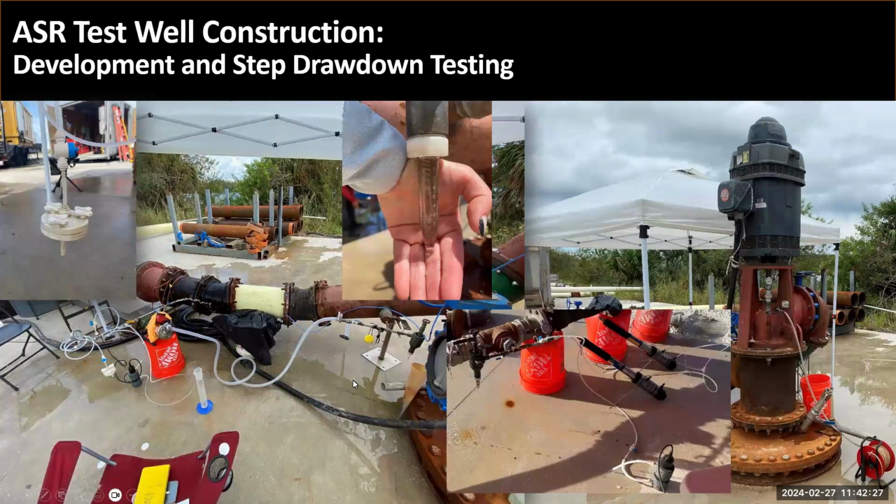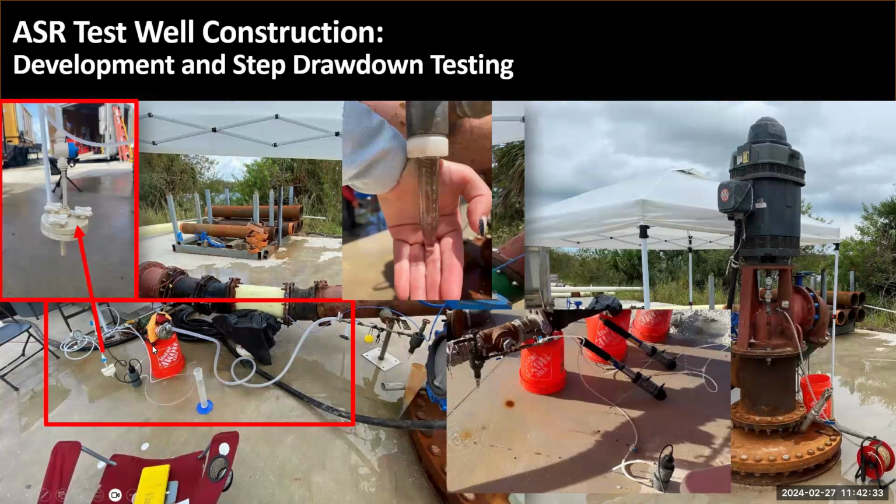This is just some images of some of the data that we collect. Over here on the left side is the SDI press. There's a little filter that goes in here. There's a pump right here. Water is pumped through this at a specific pressure, and silt density index is measured. It is dimensionless. It's just a number. But you want to keep it down below 3, and we'd like to even see it down below 1 when it's going into a membrane plant, because that silt will clog up a membrane very quickly.